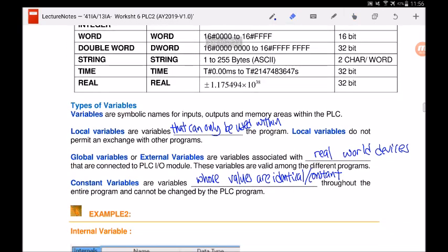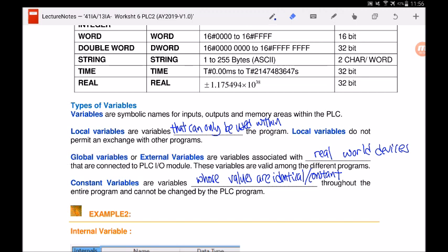Variables are symbolic names for input, output, and memory areas within the PLC. We have local variables, which can only be used within the program. We also have global variables, or external variables, which are associated with real-world devices connected to the PLC input/output module — such as solenoids, buzzers, sensors, and switches connected to the input/output card. There is also a constant variable type, whose value remains unchanged throughout the entire program and cannot be modified by the PLC.